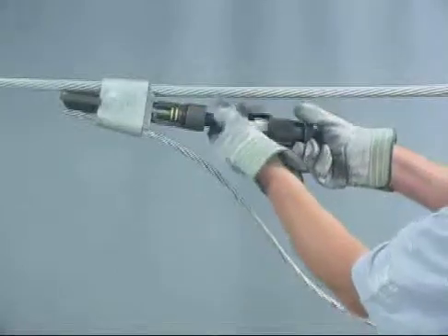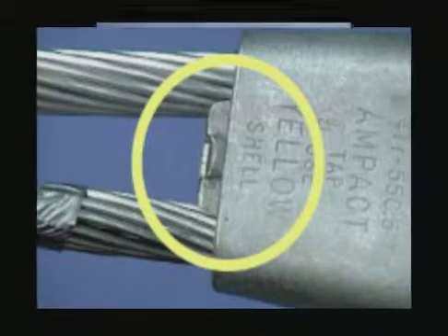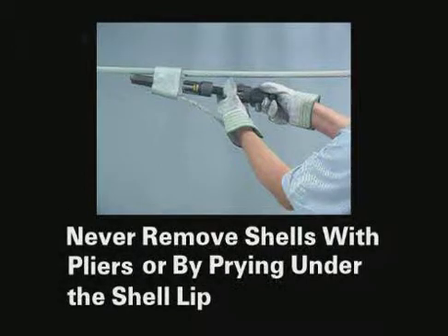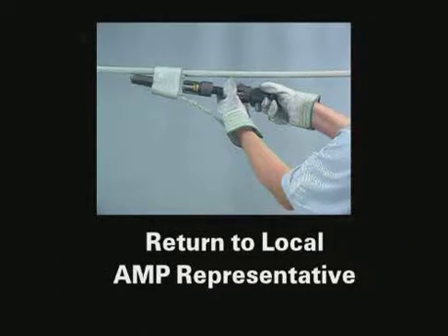All installed Ampact taps should be visually inspected for a locking tab feature. This visual indication ensures a good connection has been made. Here are some of the safety precautions to follow after firing the tool. If the gas does not release, retighten the gas release knob and strike the tool again with a hammer. When you do not get a gas release, always check the breech for a dislodged primer cap. Also, check the piercer pin's length because it may not be long enough to pierce the shell wall. Never remove shells with pliers or by prying under the shell lip. If the shell cannot be ejected, contact your local Amp representative.